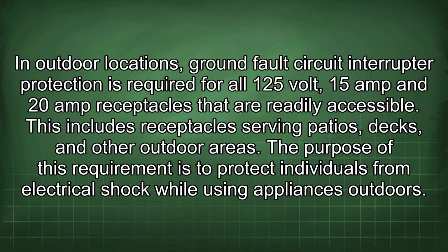In outdoor locations, ground fault circuit interrupter protection is required for all 125-volt, 15-amp and 20-amp receptacles that are readily accessible. This includes receptacles serving patios, decks, and other outdoor areas. The purpose of this requirement is to protect individuals from electrical shock while using appliances outdoors.